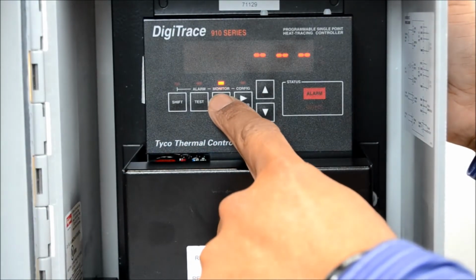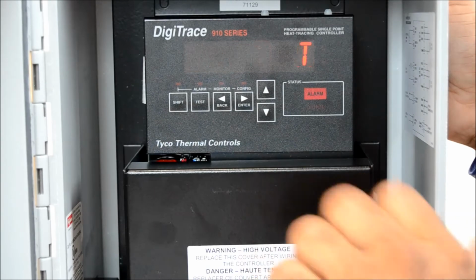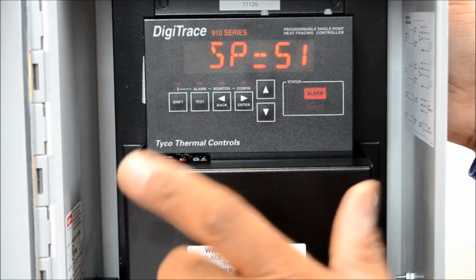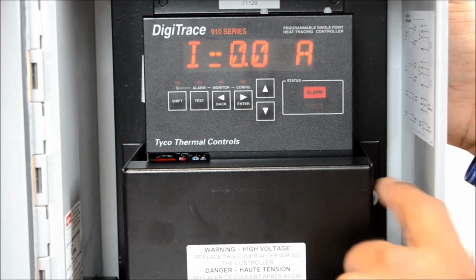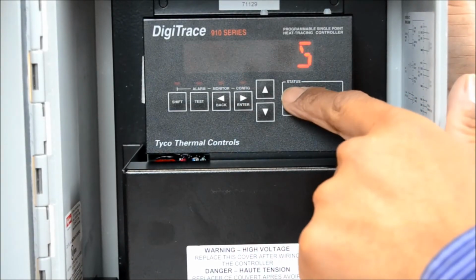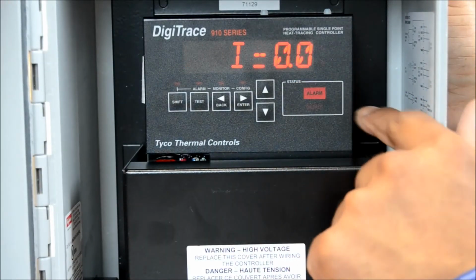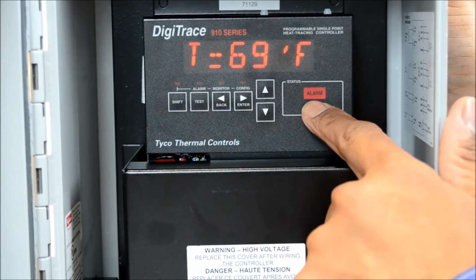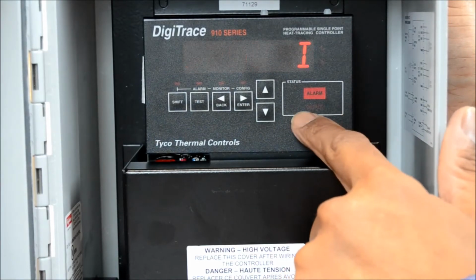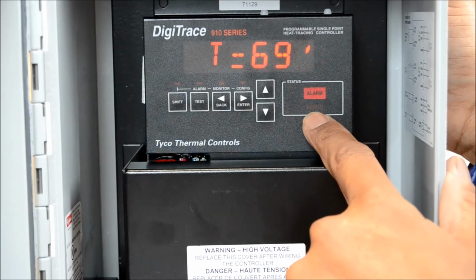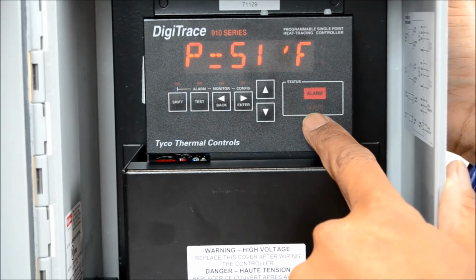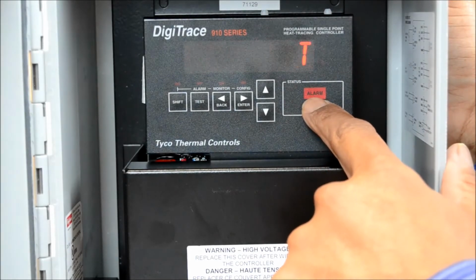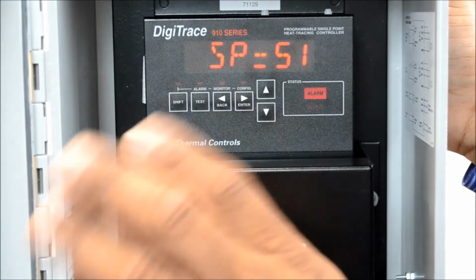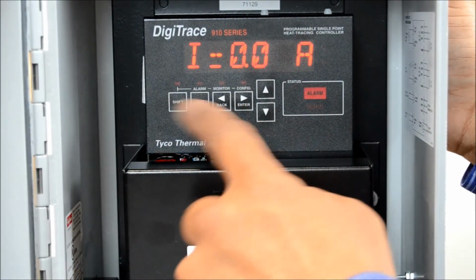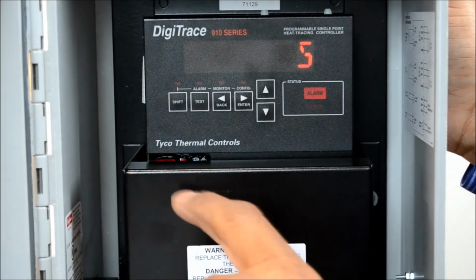Now, if you want to get out of this menu, you always hit the back key out of any menu that you try to get out of. Now let's do this. Let's cut the heat trace on. Over here, you have the status bar, which you may not be able to see, but it's a light for an alarm and it's a light for output. When the output light is on, that means the heat trace is on. When the alarm is on, of course, you have an alarm. We'll talk about how to activate the alarm system and how to clear it later on.